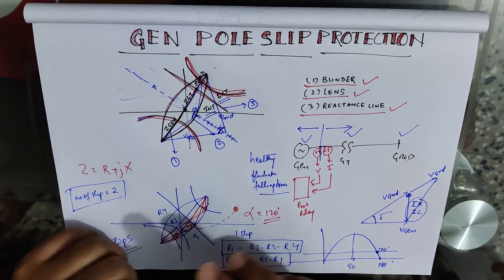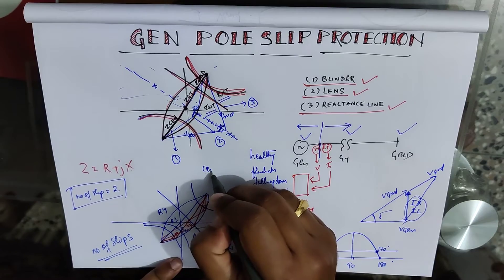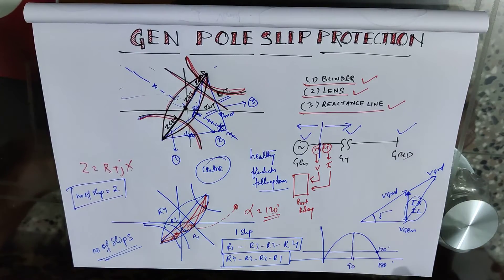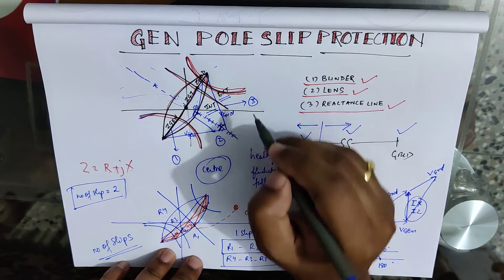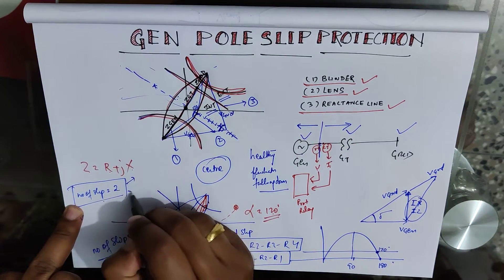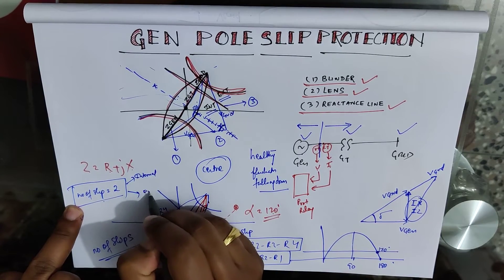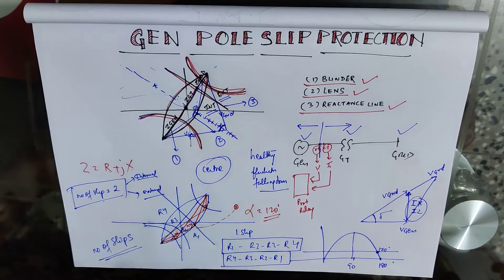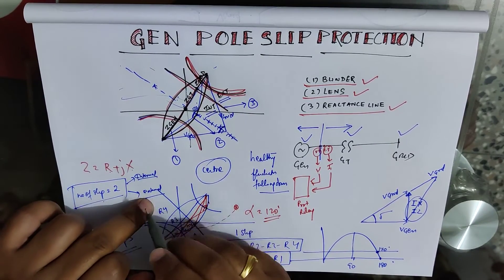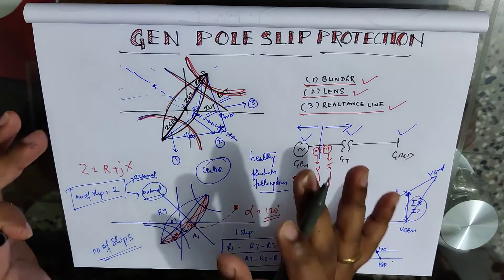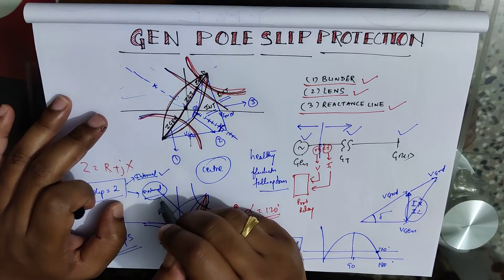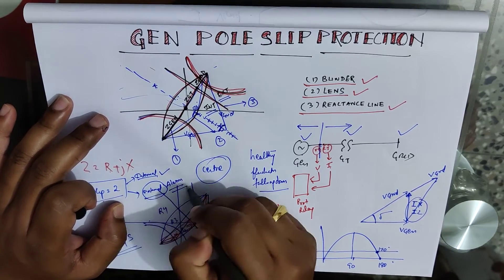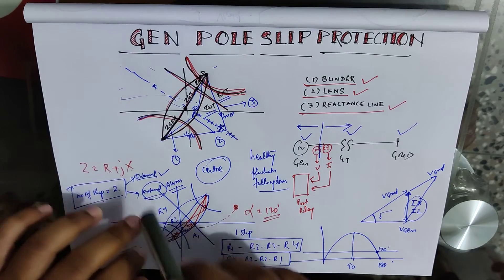The relay can also distinguish the center of the swing — it distinguishes using the reactance line. The settings are divided into two parts: internal slip setting and external slip setting. It is not recommended to trip on external slip; you should only trip the generator on internal slip. The external slip setting can be kept for alarm purposes only.